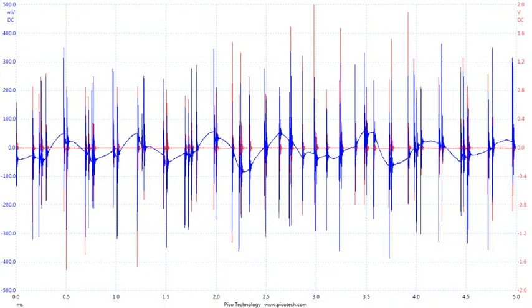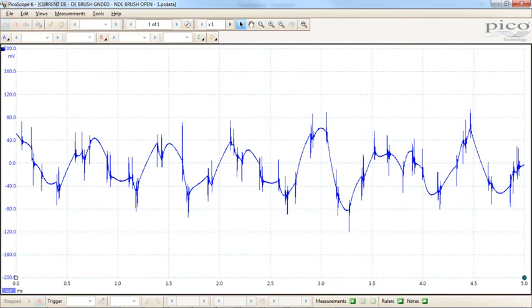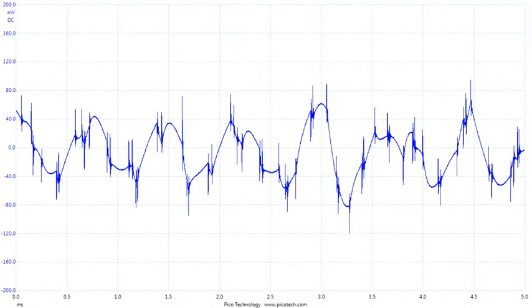Okay. This is the current. Just trying to remember, I didn't label that. Okay, that's the same one. This is the current on the drive end with the drive end brush grounded. In other words, what we're doing is we're seeing how much current the drive end brush is conducting. Okay, and that's 80 millivolts, which is 0.8 amps.